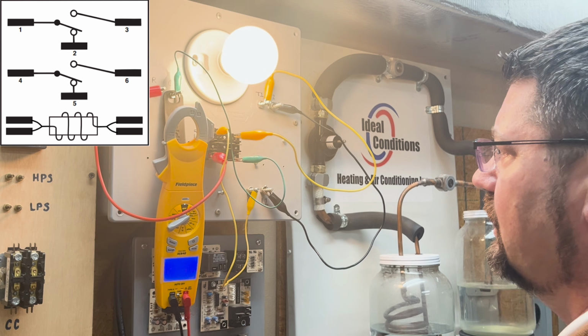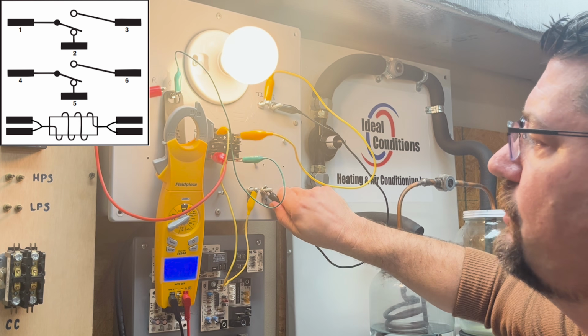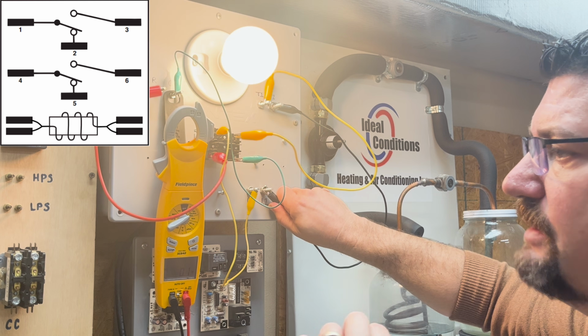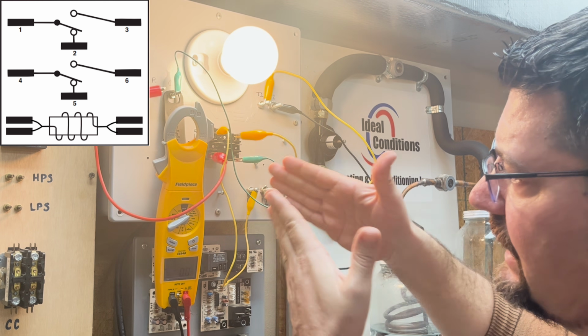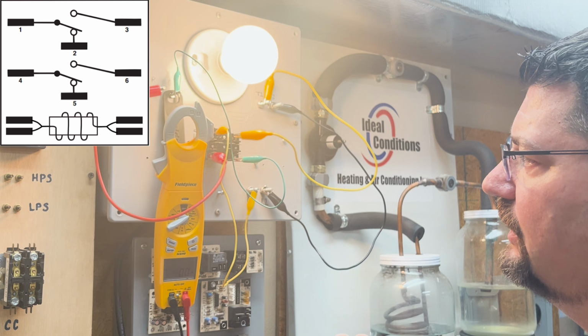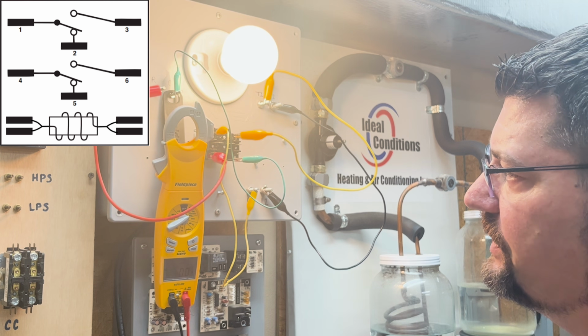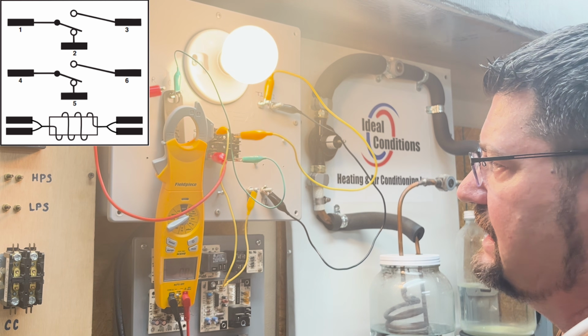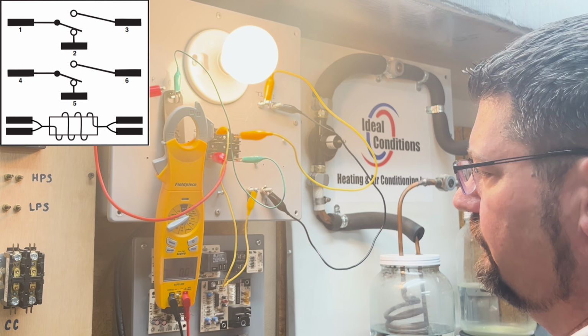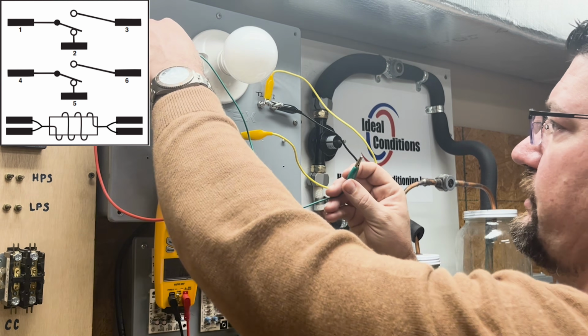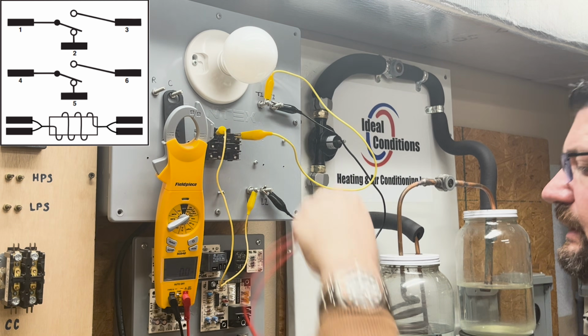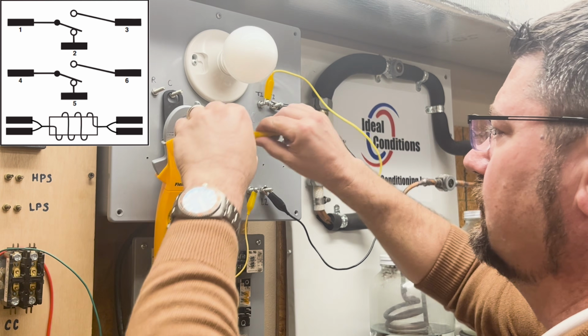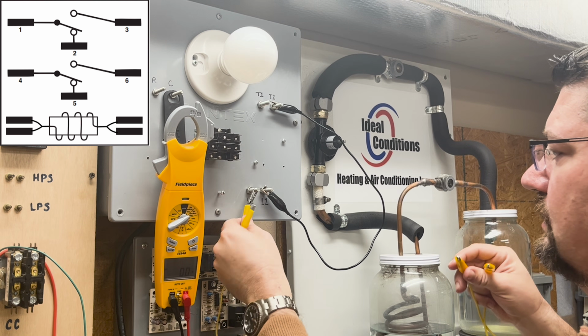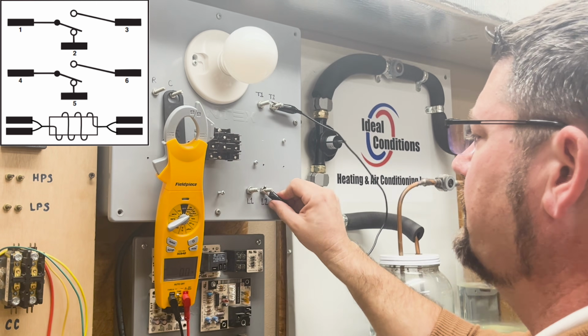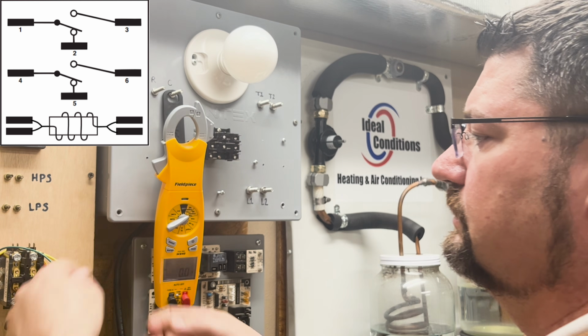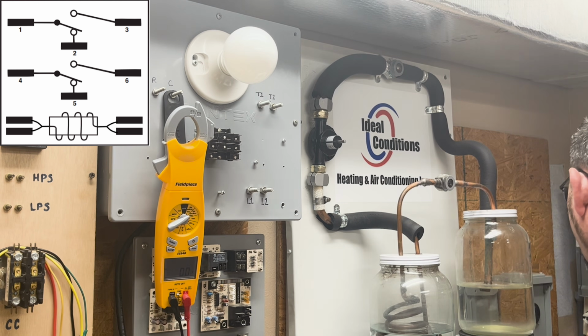So I'm now going to undo these, and I want to show you contact voltage, and I want to show you coil voltage utilizing your meter, because sometimes the diagram's not available, even though they give you a nice diagram on the very face of this relay. It's very hard to not understand normally closed and normally open, look at the face of this relay and not understand what that means. So I'm going to go ahead and just remove all the power off this relay, since we're done talking about the power portion. Go ahead and remove L2, T2. I'm going to go ahead and turn the power off for safety.